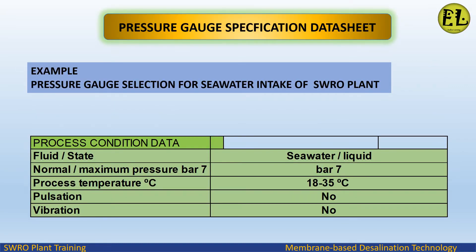Pressure gauge specification data sheet example: pressure gauge selection for the seawater intake of a SWRO plant. Process condition data — fluid: seawater, state: liquid, normal/maximum pressure: 7 bar, process temperature: 18 to 35 degrees Celsius, pulsation: no, vibration: no.